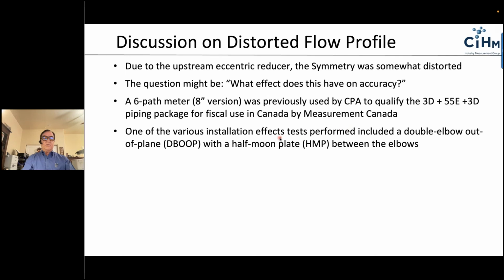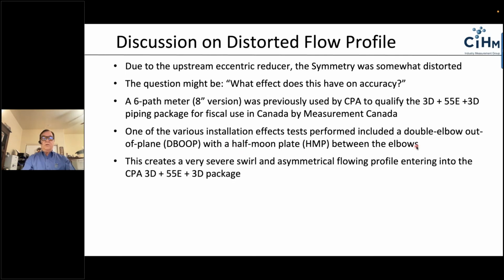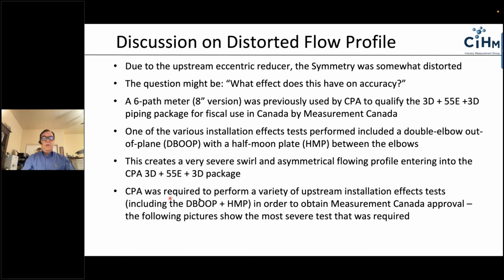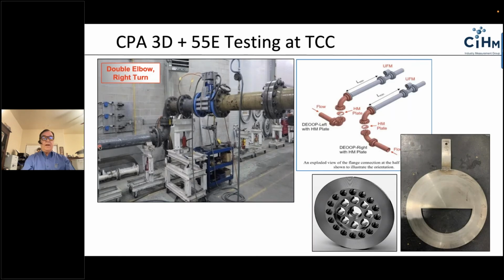This one particular test sort of replicates the worst case scenario. Wayne likes to call this the D-boop, the double elbow out of plane, and then the half moon plate in the middle creates a nasty distorted profile. So these are part of the tests that were required by Measurement Canada in order for CPA to obtain approval to install an ultrasonic meter with the 3D 55E 3D package. So CPA was required to provide a variety of tests. I'm just going to show you the worst case scenario test here and give you a couple of pictures to show you what the piping looked like.